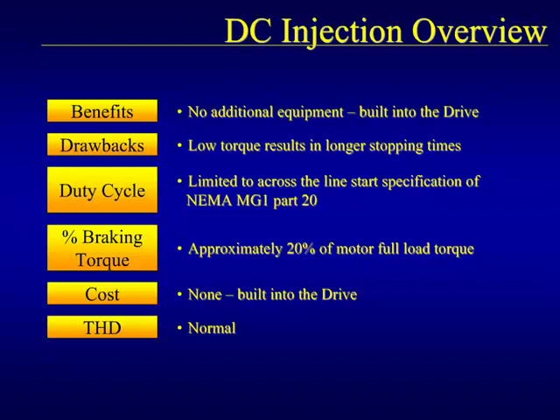However, DC injection has low braking torque compared to the other braking methods, which yields longer stopping times. The duty cycle is also dependent upon the specifications of NEMA MG1 Part 20. Motor sizing and parameter configuration determine the actual duty cycle for the DC injection function.